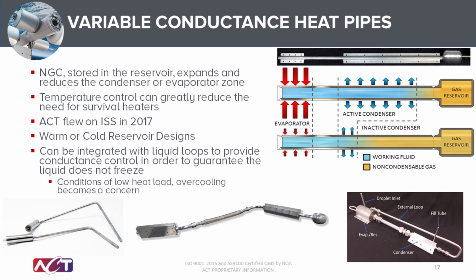Variable conductance heat pipes, touched on a couple of times here, or VCHPs. The main purpose of a VCHP is to save you battery power when it gets cold. A VCHP varies the conductance by increasing and decreasing the condenser length. If you picture a constant conductance heat pipe as this heat pipe here, but without the gas reservoir, the one challenge of CCHP production historically has been to remove all NCGs, or non-condensable gases, from the system, because NCGs are always considered bad in a CCHP. You don't want NCGs. But for a VCHP, we can actually introduce them intentionally, and really what we're doing is making the heat pipe less effective when it gets cold.